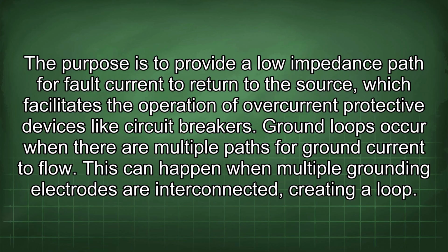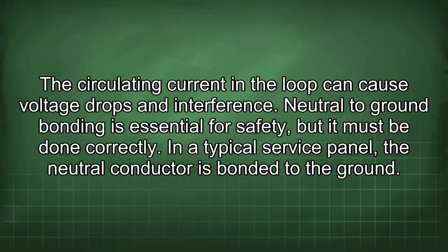Ground loops occur when there are multiple paths for ground current to flow. This can happen when multiple grounding electrodes are interconnected, creating a loop. The circulating current in the loop can cause voltage drops and interference.